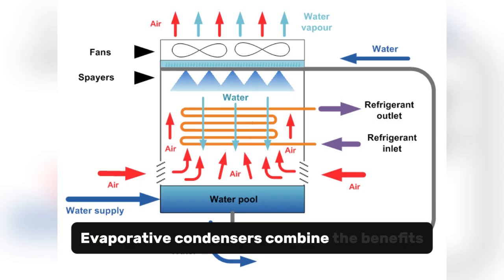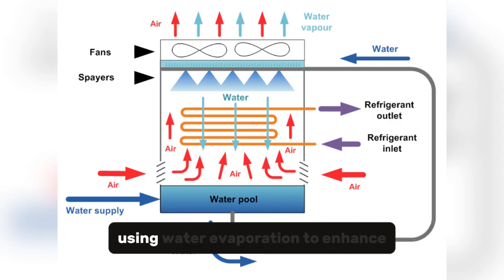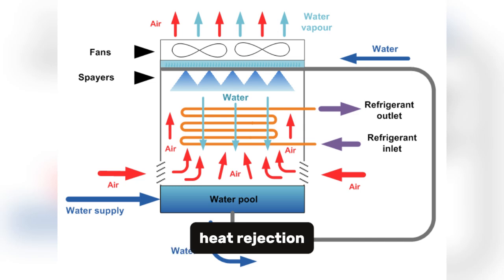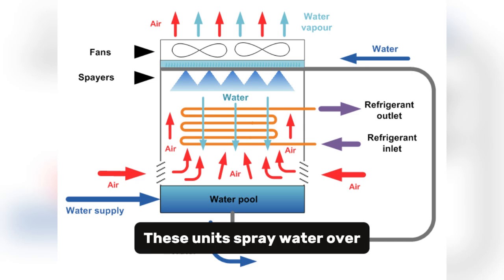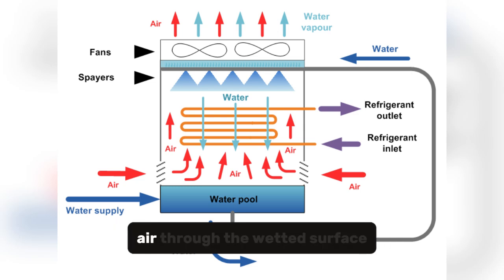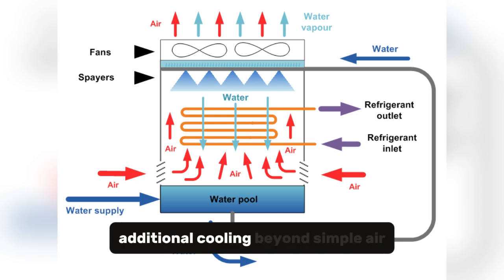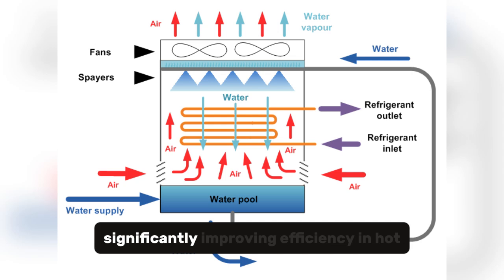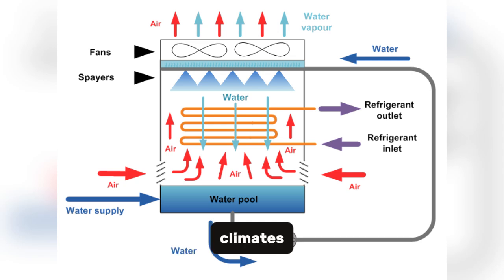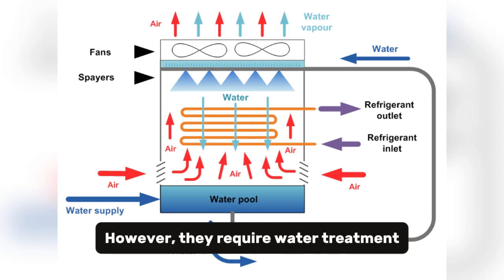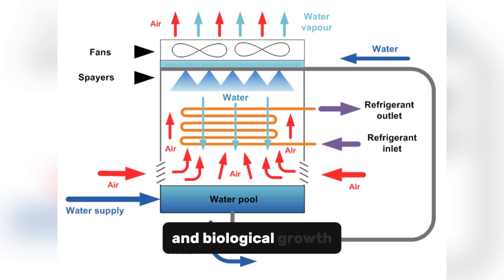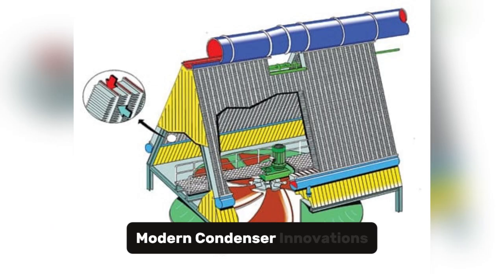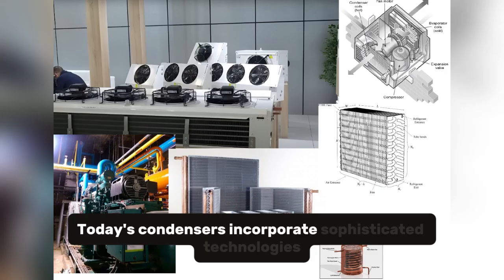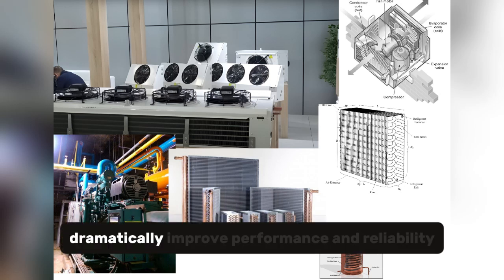Evaporative condensers combine the benefits of air and water cooling by using water evaporation to enhance heat rejection. These units spray water over the condenser coils, while drawing air through the wetted surface. The evaporation of water provides additional cooling beyond simple air cooling, significantly improving efficiency in hot climates. However, they require water treatment and maintenance to prevent scaling and biological growth. Modern condenser innovations. Today's condensers incorporate sophisticated technologies that dramatically improve performance and reliability.